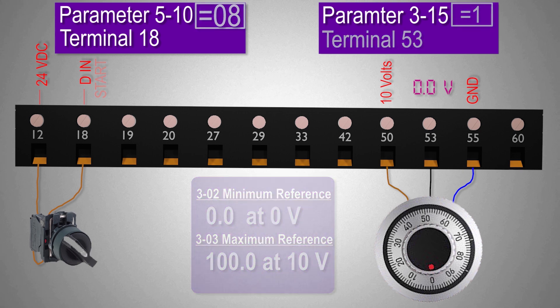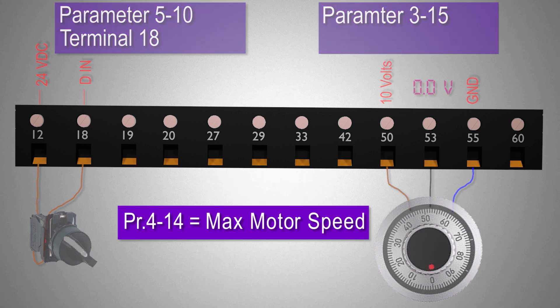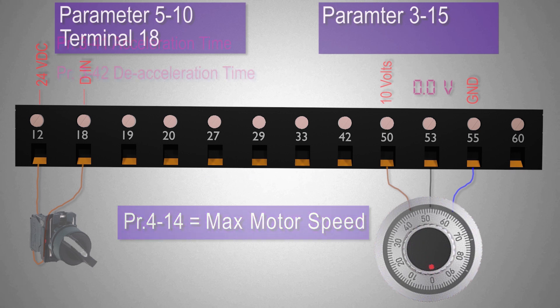Just a side note here, the speed of the motor will not exceed the speed which we have entered in parameter 4-14 which is the maximum speed limit. If we want to run at high speeds we have to increase the speed limit in parameter 4-14.